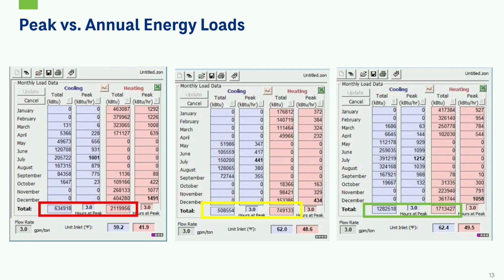Whereas when we look at the third graphic, it looks like we have a peak cooling load of 1,200 kBTUs per hour in July, and then we have a peak heating of about 1,100 kBTUs per hour. So just looking at these peak loads, I would say, oh, we're probably going to have a cooling dominant building because our peak cooling load is a little bit larger than our heating, but maybe it's somewhat balanced. And if you look at the annual loads, we actually have about 1,300,000 kBTUs for cooling, but we actually have more heating load annually, about 1,700,000 kBTUs for the heating annual load.